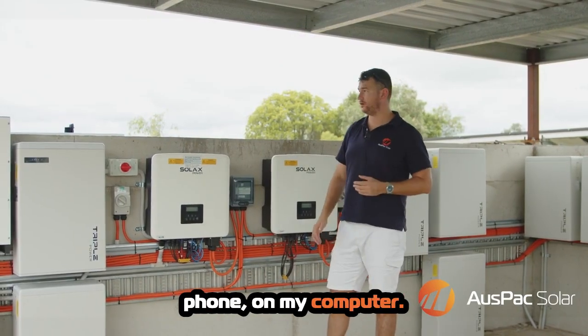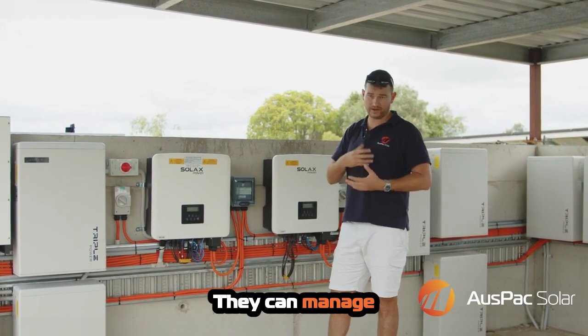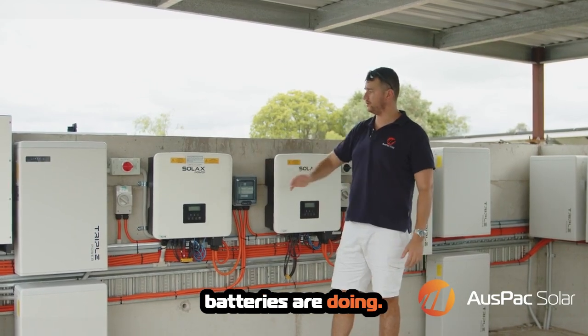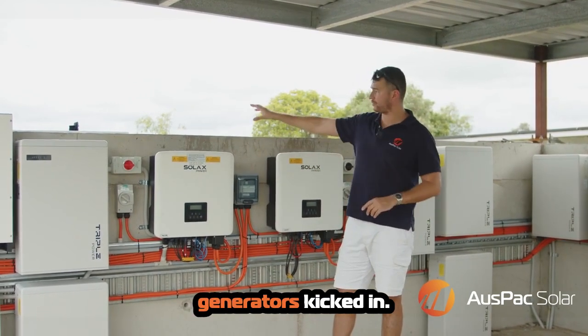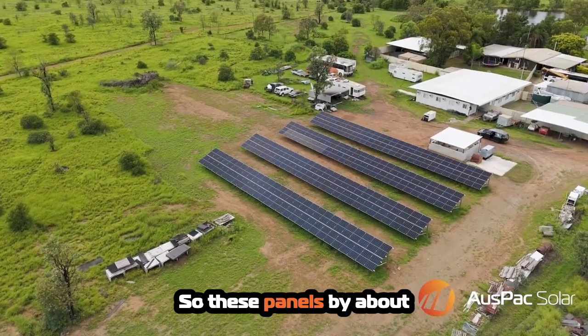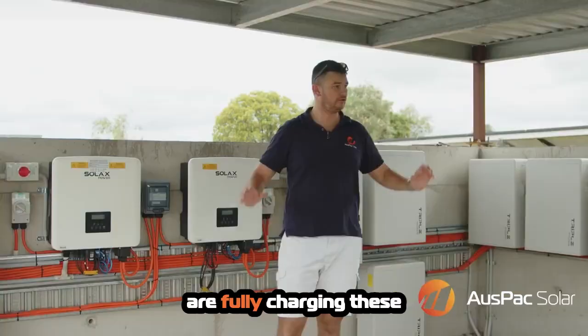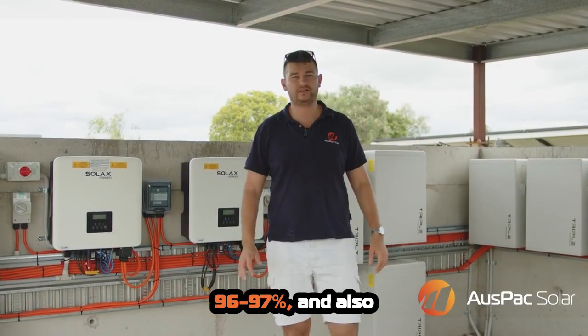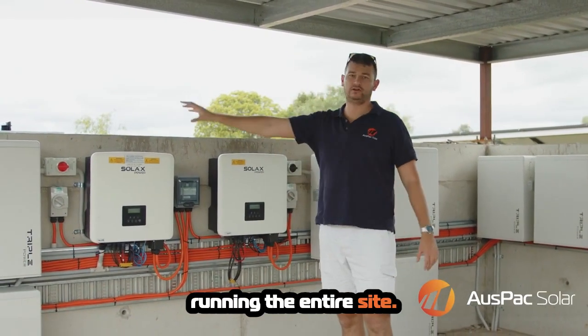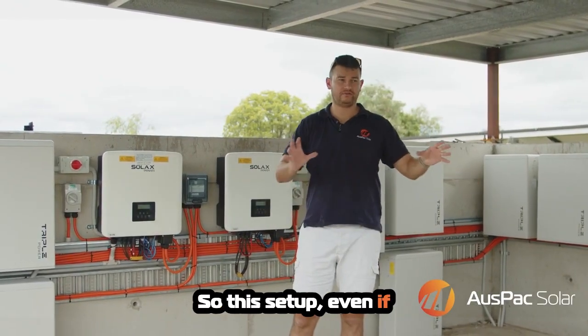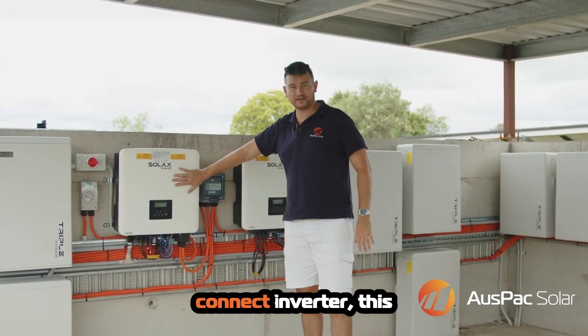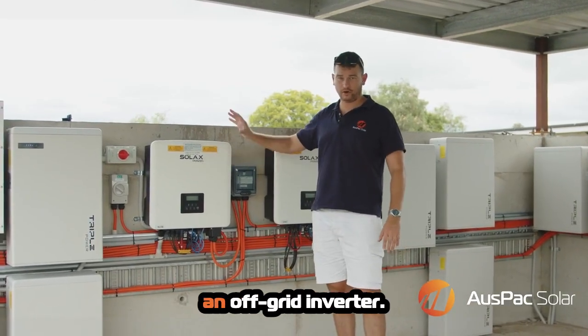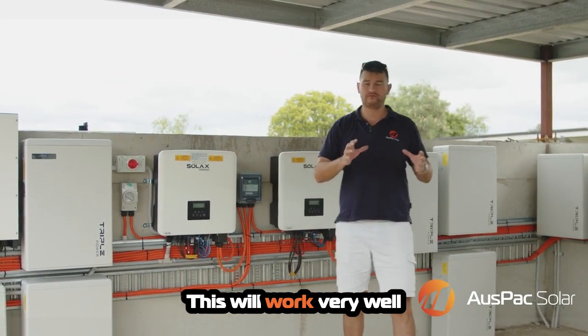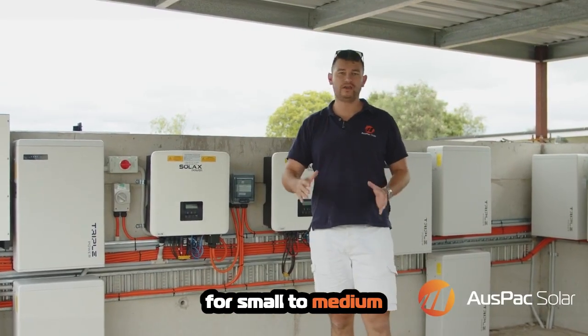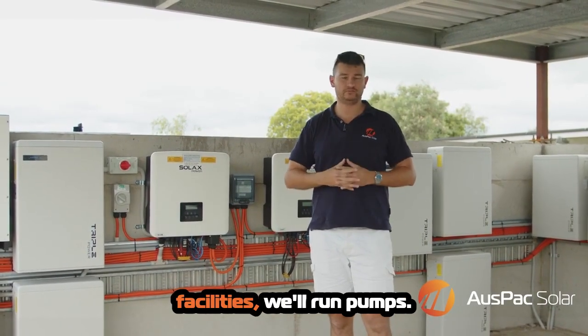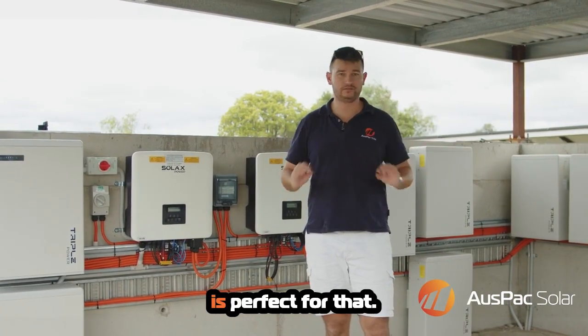When we're reading the system on our portal, so I check this every week, for instance, on my phone, on my computer, the customer has access, they check it all, they can manage their own energy. We can see what the batteries are doing, we can see what the inverters are doing, we can see when the generator's kicked in. So these panels, by about 9:30 in the morning, are fully charging these batteries up to around 96, 97%, and also running the entire site. So this setup, even if they are grid connected, because this is a grid connect inverter, this is a battery connected inverter, and this is an off-grid inverter. This will work very well for small to medium agriculture, commercial facilities will run pumps. This setup, this design is perfect for that.